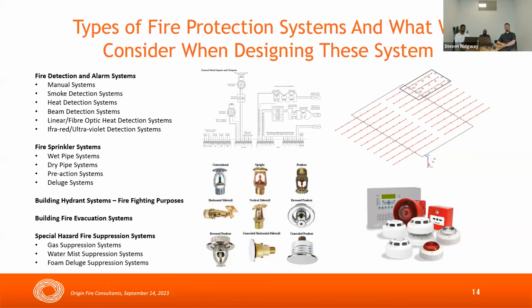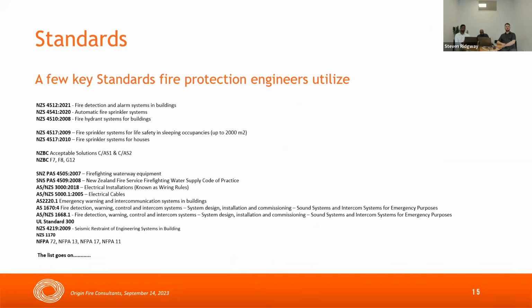Engineers must be able to conduct a variety of complex calculations in order to verify a fire protection system's design and seek approval from system certifiers. There are various standards associated with the different types of fire protection systems in New Zealand. These standards cover the design, installation, compliance, maintenance, and ongoing testing for such systems. A few key standards in New Zealand are NZS 4512, which is fire detection and alarm systems in buildings. The second one is NZS 4541, automatic fire sprinklers, and 4510 for fire hydrant systems in buildings.